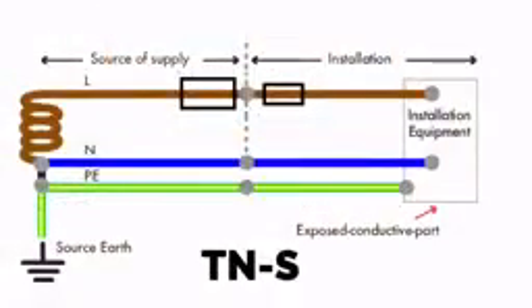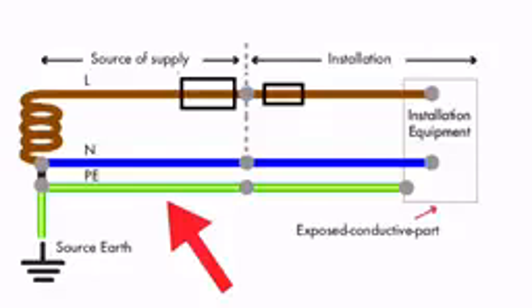TNS earthing arrangement, earth and neutral are separate. The supply authorities provide us with a separate protective earth and a separate neutral conductor into the installation. If this is what it looks like in a single phase domestic dwelling, how will it look in images shown to us for our exams? The left hand side of this drawing shows the supply authority's cable with a separate line conductor, a separate neutral conductor and a separate protective earth conductor coming into our installation.